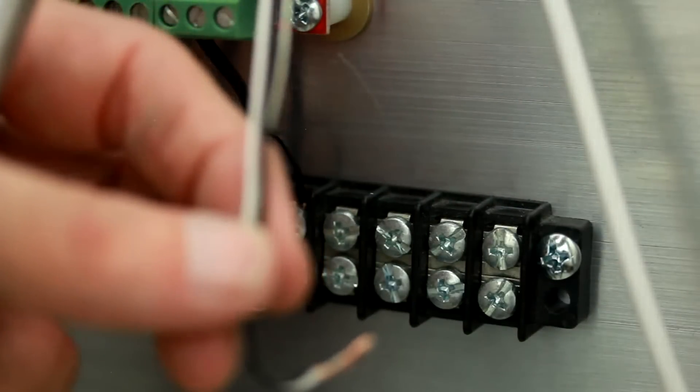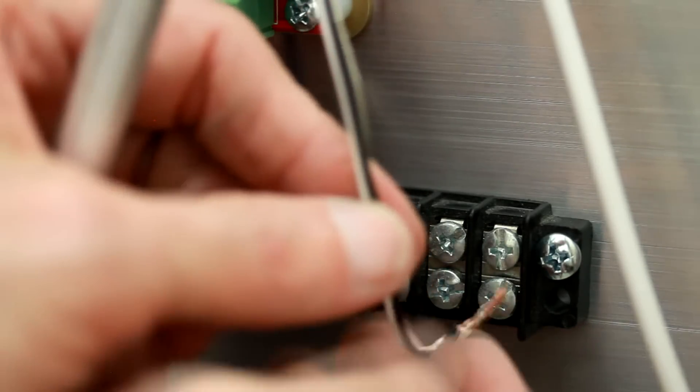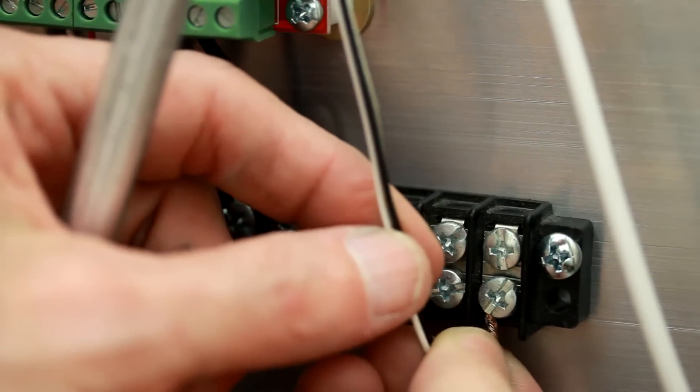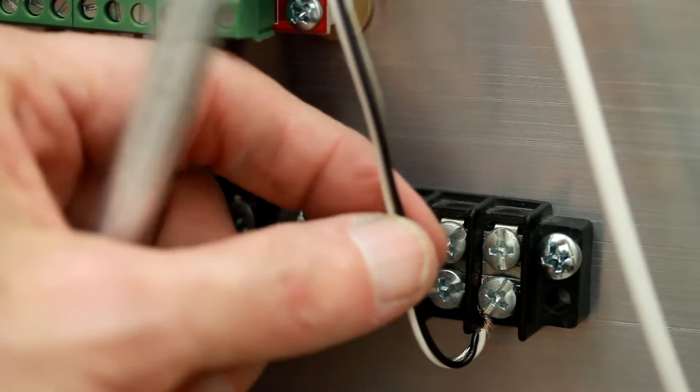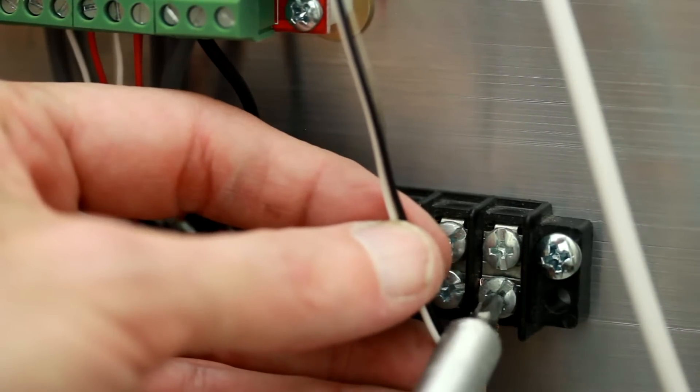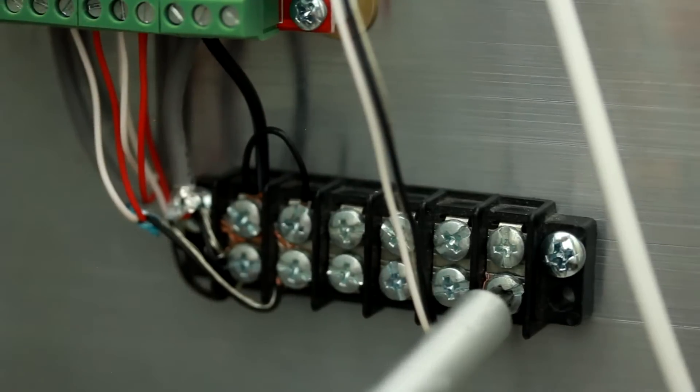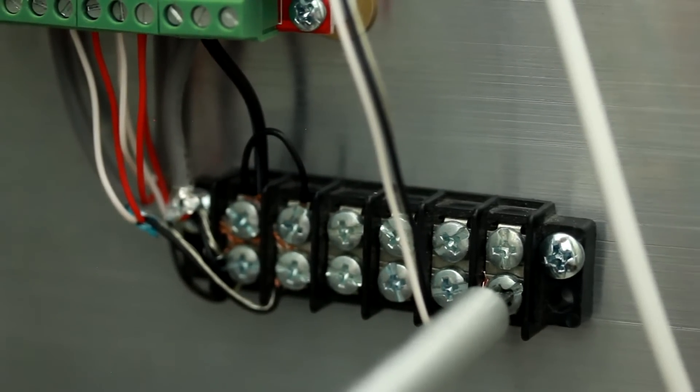The black wire and any other wires and shielding in this cable, I'm connecting to the ground terminal block, but it's not going to be connecting to the digital ground, it's going to be connecting to the 24 volt ground. So I'm not going to connect this side of the terminal block to the other side that was used for the motion and the drivers.